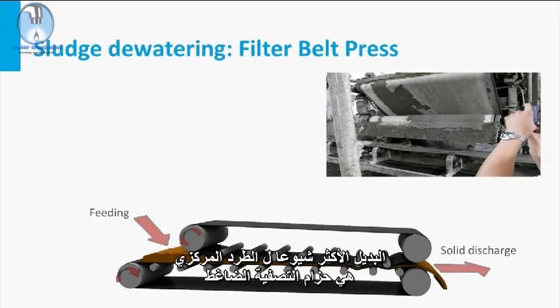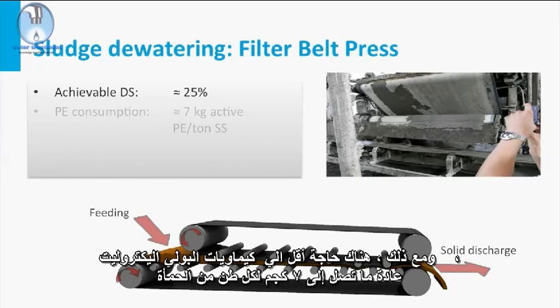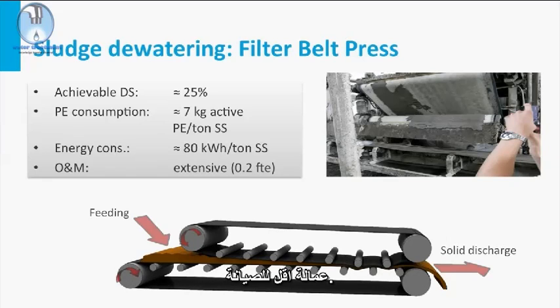The most common alternative to centrifugation is the filter belt press. Also with a filter press, a dry solids content of about 25% can be achieved. However, less PE chemicals are required, generally up to 7 kilograms per ton sludge. The energy consumption is also a little bit lower, reaching 80 kilowatt hours per ton SS, and less personnel is required for maintenance.